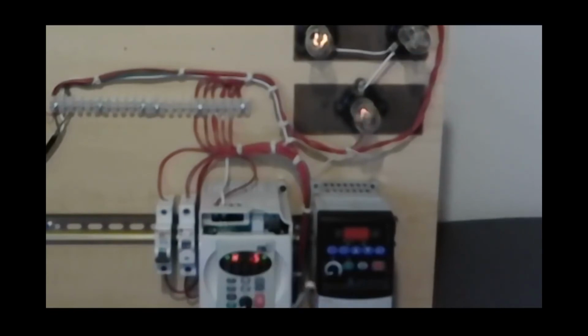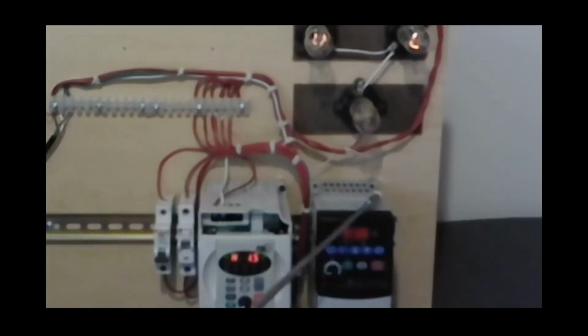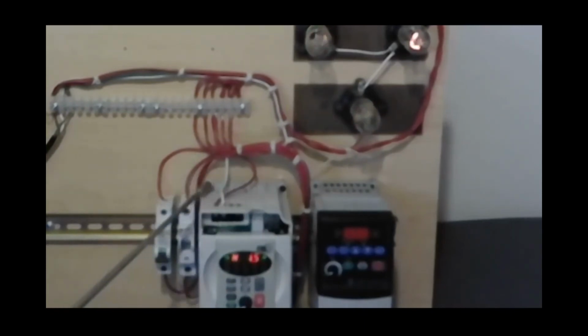If one drive starts the same time another one starts, or they start and stop at the same time, very easily the transient voltage from one drive can kill the next. So we might have to have some type of power filter upstream of the drive. Now, drives themselves, you look at all the vents, these two drives are exposed to the elements. If I'm in an area that's dirty, dusty, unclean, then our circuit boards here are going to gather a lot of dust and dirt and contaminants very quickly.